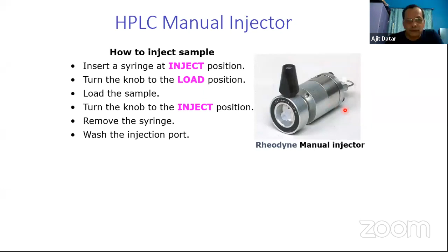This injection port is connected to the chromatography in such a way that after filling the loop, the mobile phase will pass through the loop and take the sample from the loop to the column and then to the detector. Because your mobile phase is at higher pressure, you cannot use a direct syringe as you can in gas chromatography. So you have a loop here. This is the way the design is.